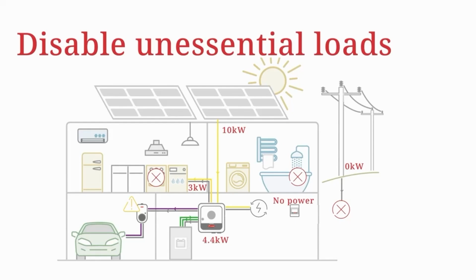So what can we do to prolong the availability of the battery? Well, first of all, we can reduce the amount of load on site by switching off unneeded equipment such as an oven or maybe a power shower. Also, we can make sure that any EV chargers are either in fallback mode or on non-essential circuits within the building which are not backed up by the PV system. Then we're only powering those most important things, maybe the lighting, your fridge freezer, a boiler, to make sure that you're going to get the maximum life out of that battery before it can recharge.